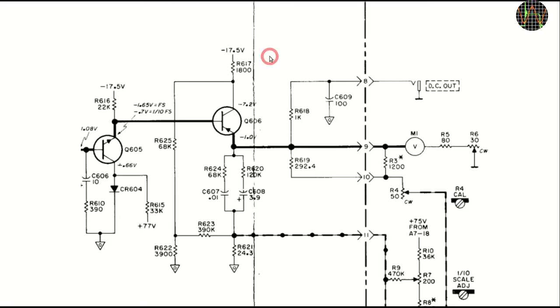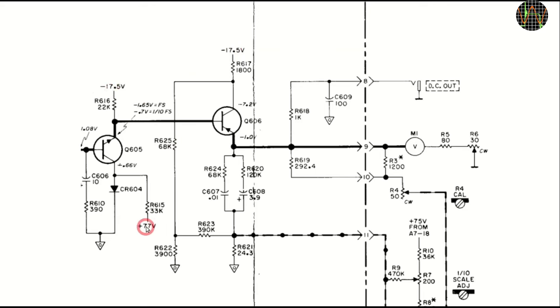The HP3400A uses weird voltages of minus 17.5V for most electronics and a second rail of plus 77V. There is actually a third rail of plus 6V but that is a rather sensitive stabilized voltage for the heater of the tube in the input circuit. Yes, this meter has a vacuum tube. Because even small changes in the heater voltage would directly influence accuracy, that heater circuit is best left alone.